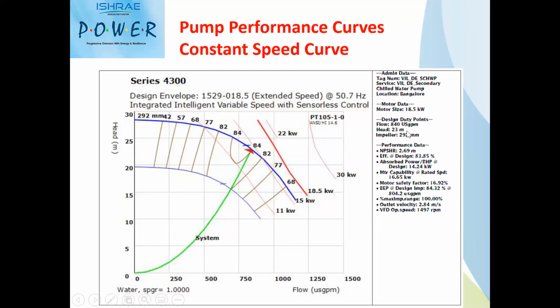captured when we are having pump performance curves? They are the NPSH values. The NPSH is net positive suction head required, efficiency of the pump, then absorbed power of the pump. Absorbed power is nothing but BKW. To have a flow and head of 840 at 23, what is the typical power required? Here in this case, it is 14.24.